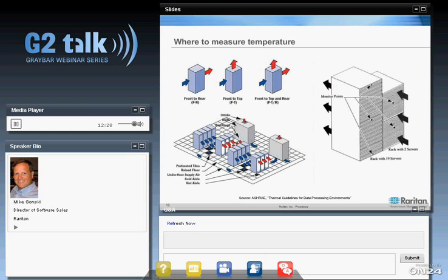Looking at where to measure: per ASHRAE's Thermal Guidelines for Data Processing Environments, in a standard rack we want to measure at the top, middle, and bottom on the inlet side. Raritan recommends a simple sensor called the T3H1, which connects via an RJ11 connection to our rack PDUs or environmental units. It's very inexpensive — a sensor costs just a little over $100.